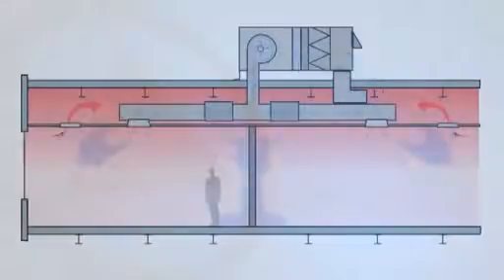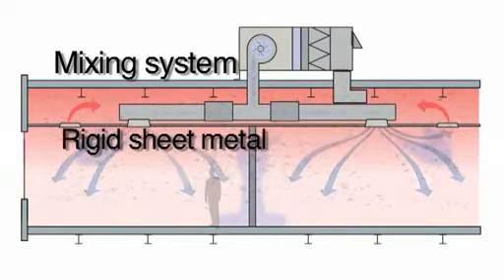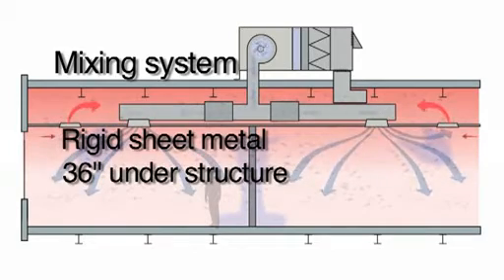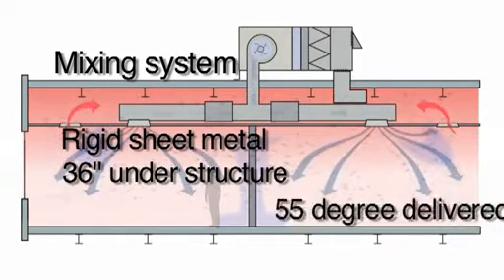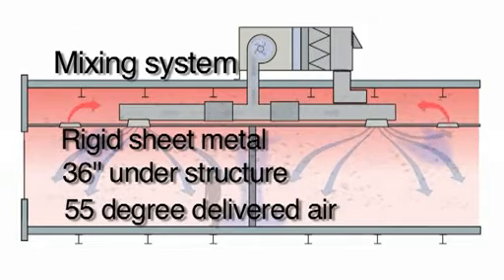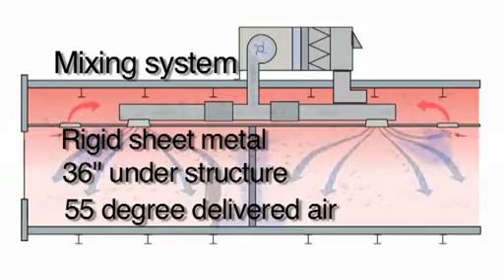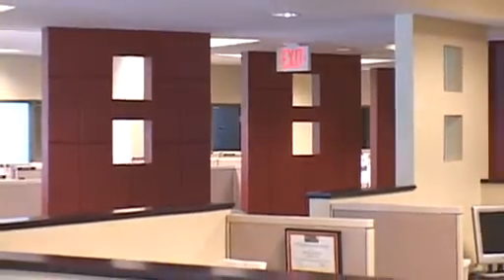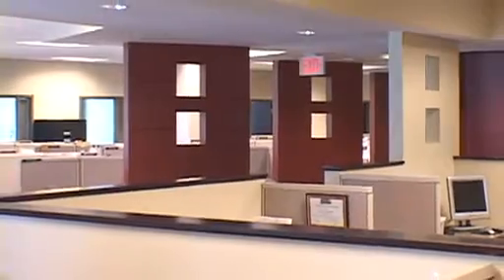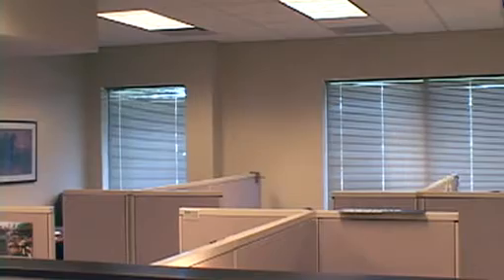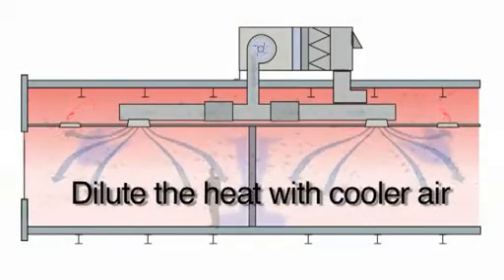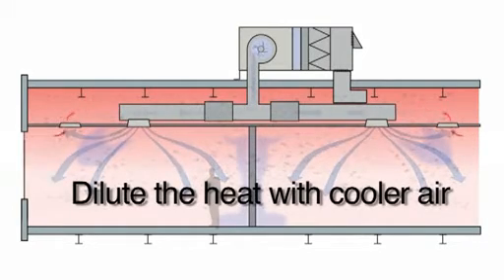Overhead ducted systems are generally mixing systems with a lot of sheet metal and the labor to fabricate and install it. Occupying about 24 to 36 inches below the structure, they usually deliver 55-degree air at relatively high velocities through diffusers mounted high in the space. These systems push large amounts of conditioned air into the existing occupied air space that is being heated by people, electronics, lights, exterior walls, etc. The job of a mixing system is to dilute that heat back into the space with enough cooler air to maintain the desired space temperature.